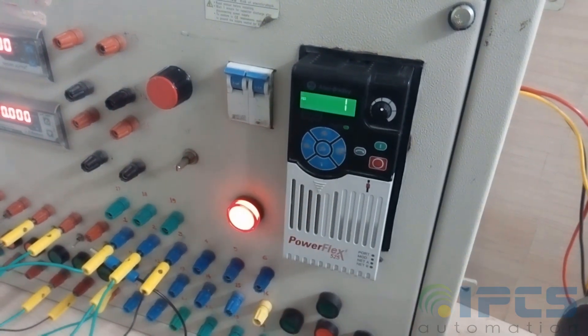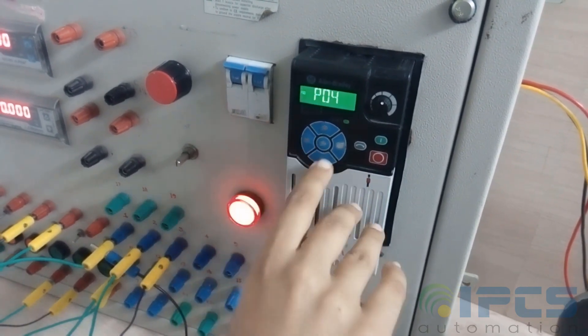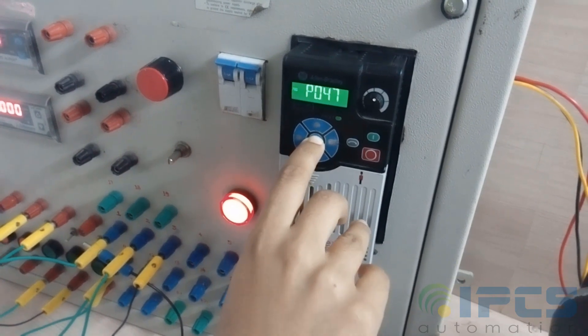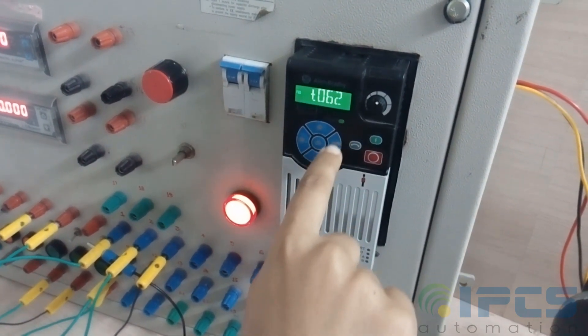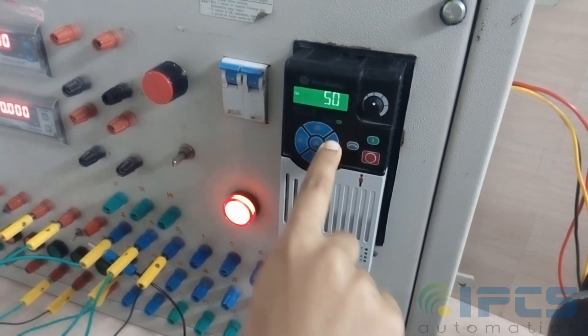Also set P047, the speed reference, to drive pot for convenience. The digital blocks 2 and 3 can be used for two-wire operation. Use T062 and T063 and set them to 48 and 50 respectively.